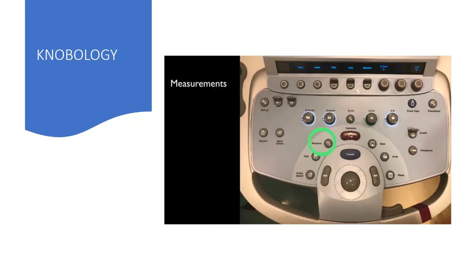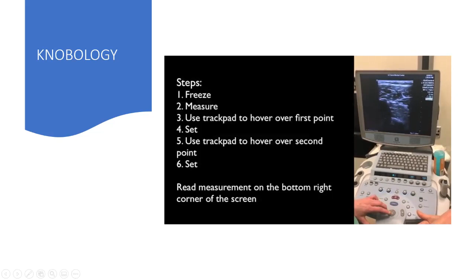Using the measure feature can be helpful in determining vessel diameter, gallbladder wall thickness, fetal crown to rump length, and more. First, freeze your image, press the measure button, use the trackpad to hover over the first point and press set to drop your caliper. Then, use the trackpad to span the distance you want to measure and hit set again to drop your second caliper. The measurement will be displayed at the bottom right of the screen.